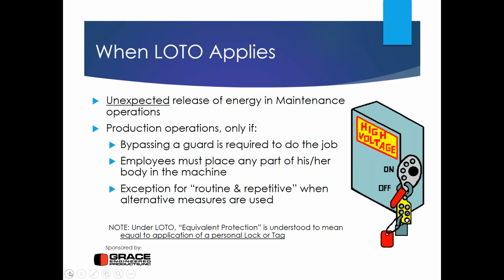However, the note at the bottom of the slide is particularly important, and the term equivalent protection exists in OSHA on several levels. The assumption is that if there is a situation where legitimately you cannot follow lockout, tagout as designed, you would be required to come up with an equivalent system. And the equivalency that we're shooting for is meant to be the protection of actually installing a personal lock or tag as well. So we'll cover the idea of equivalent protection more than once in the presentation.